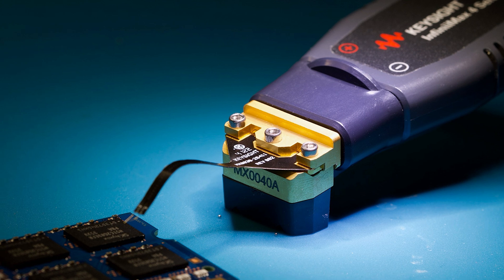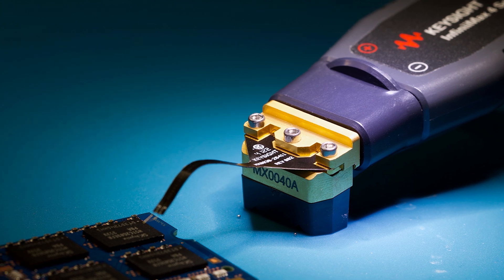Absolutely, Courtney. The InfiniiMax 4 represents the pinnacle of Keysight's technological innovation. It leverages Keysight's proprietary indium phosphide IC process technology, which is at the cornerstone of its exceptional performance. But it's not just about our custom ASIC design. We've completely revamped the entire modular probing system. It now features a removable, flexible PCB probe head, enhancing its versatility and ease of use. This design streamlines the connection of the amplifier to different probe head connectors.